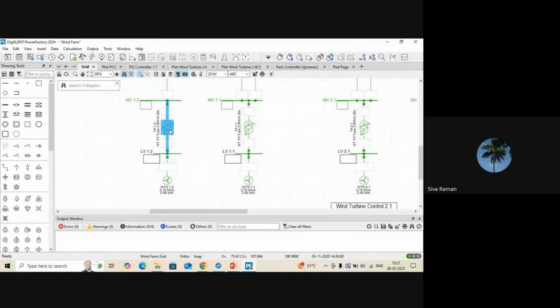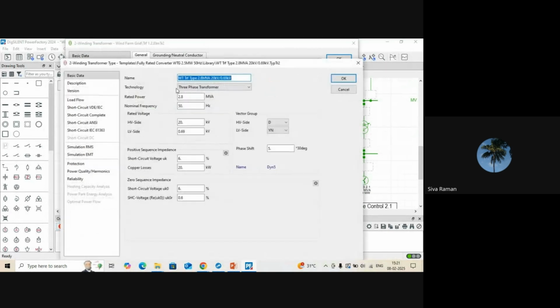Then the wind turbine transformer. In the wind turbine transformer, it is 2.8 MVA. Its voltage is 20 kV at the high voltage side and 0.69 kV at the low voltage side. Vector group, high voltage side it is delta, and low voltage side it is star grounded. And for its impedance, this one is the short circuit voltage UKH and impedance 6%, and it has a copper loss of 20 kilowatt. This is for the positive sequence, and the bottom one is for the zero sequence. For doing the harmonic study, we have to model the positive sequence as well as the negative and zero sequence.